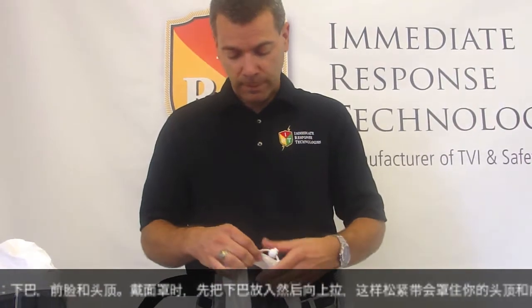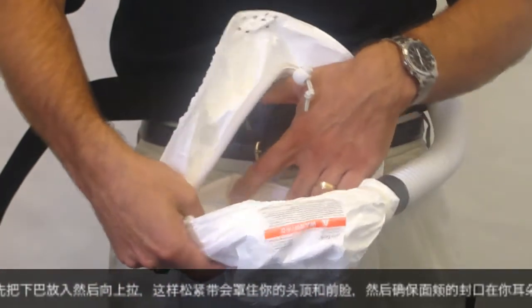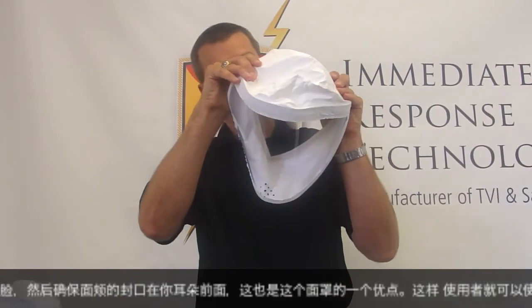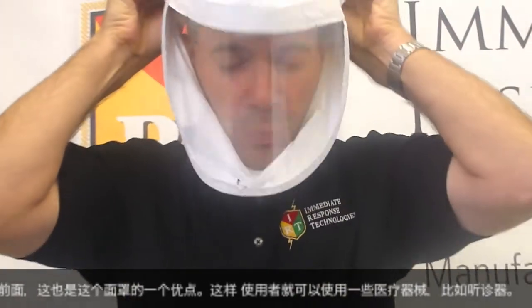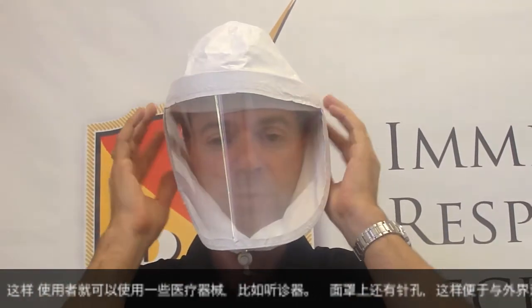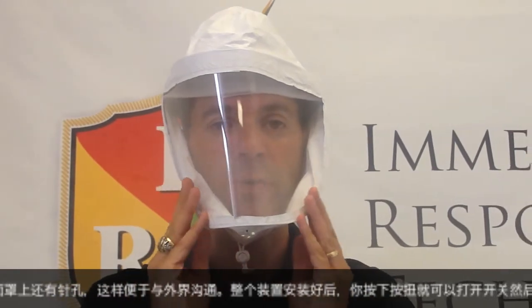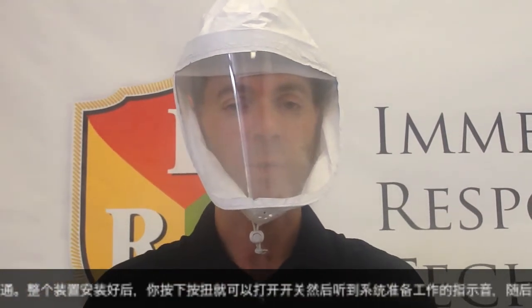The loose-fitting visor has three adjustments: an adjustment for the chin strap, an adjustment for the crown of your head, and an adjustment for the forehead. To install, insert the visor at your chin, pull it up and over so the strap is across your crown and your forehead is pressed along the forehead strap, ensuring the chin seal goes in front of the ears. This allows users to use medical equipment such as stethoscopes where ear exposure is needed.